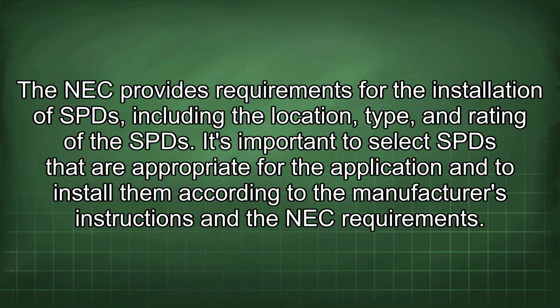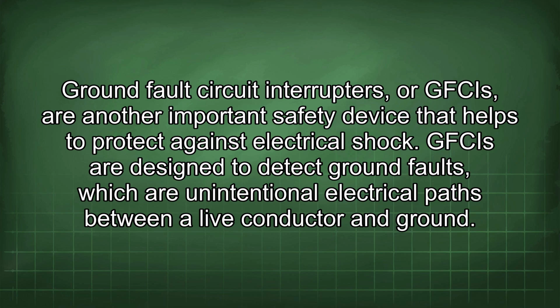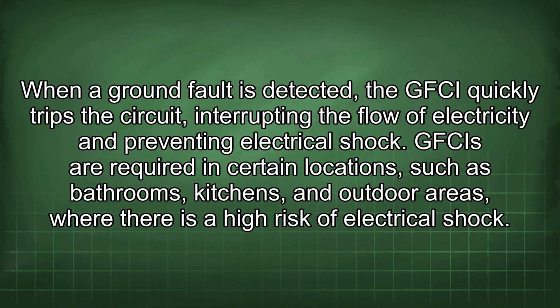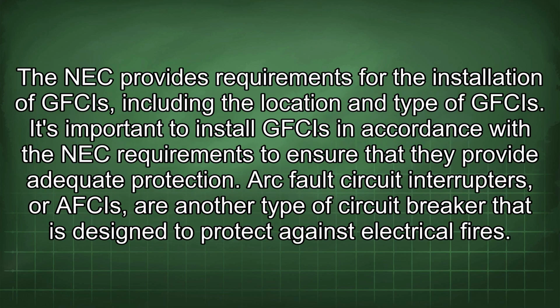and the NEC requirements. Ground fault circuit interrupters, or GFCIs, are another important safety device that helps to protect against electrical shock. GFCIs are designed to detect ground faults, which are unintentional electrical paths between a live conductor and ground. When a ground fault is detected, the GFCI quickly trips the circuit, interrupting the flow of electricity and preventing electrical shock. GFCIs are required in certain locations, such as bathrooms, kitchens, and outdoor areas, where there is a high risk of electrical shock. The NEC provides requirements for the installation of GFCIs, including the location and type of GFCIs. It's important to install GFCIs in accordance with the NEC requirements to ensure that they provide adequate protection.